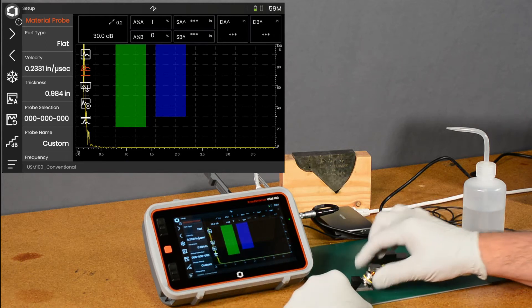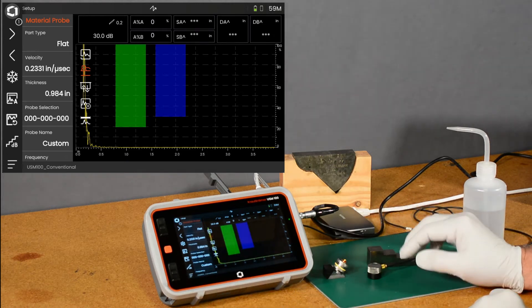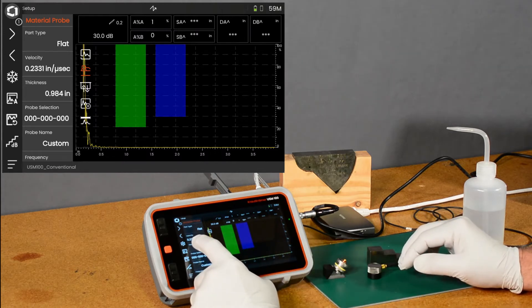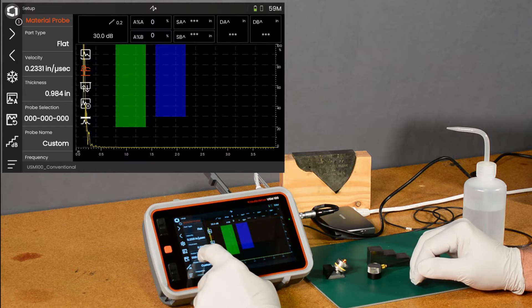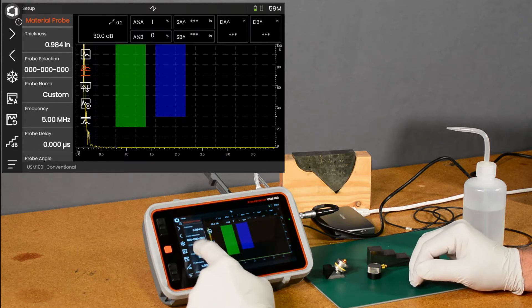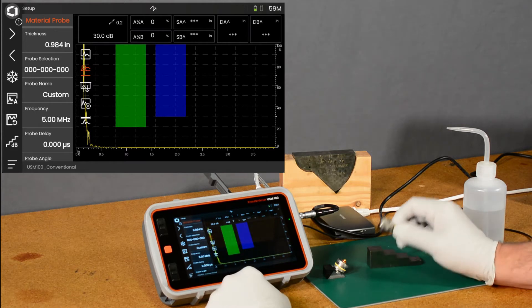but we can come in here and look at the probe setup. Because we're going to be doing a straight beam calibration on a steel block, the default velocity of 0.23 inches per microsecond is going to be close. The probe frequency is already selected at 5 MHz, so that's going to do a good job of setting the pulsar width.